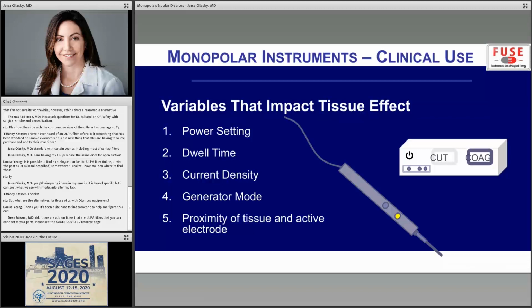And the power setting, with the higher power setting, you want to think about higher voltage, higher risk of injuries. So we always encourage everyone to use the lowest power setting possible to achieve their desired tissue effect. And in a couple of slides, we'll go through how that's possible, because sometimes you might think you need to go up on the power setting with your monopolar instrument, but really you could just change your technique and change the things listed down here, like current density or proximity of tissue to the active electrode, and that's actually going to give you the tissue effect that you want, not just increasing your power setting.